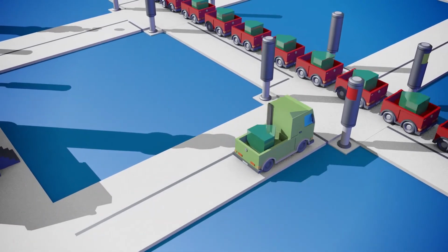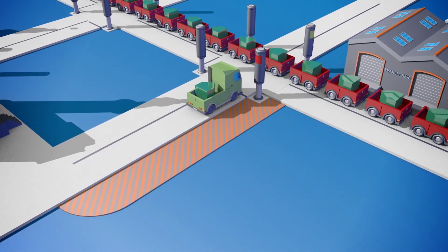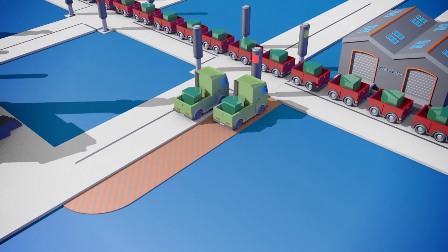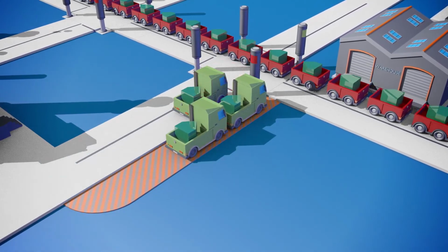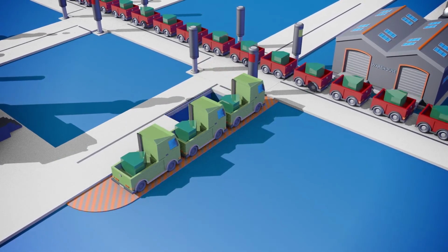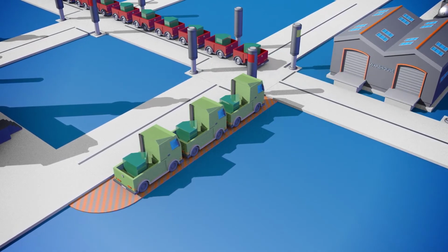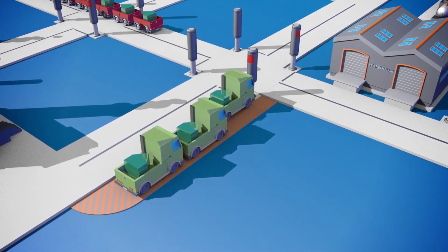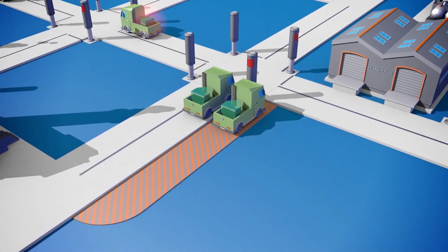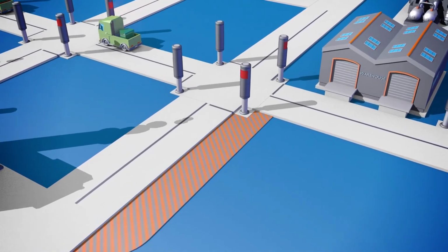This heavy load affects the behavior of the switches. Each switch has memory capacity, so-called queues. When traffic is heavy, the queue provides interim storage for the telegrams. If the load remains high in the long term, the queue becomes full and all new incoming messages are lost. These so-called discards are a sure sign of unstable communication operations. When the traffic load decreases, the queue gradually sends the stored telegrams to their destination. This is because only one telegram at a time can be sent on each section of the route.